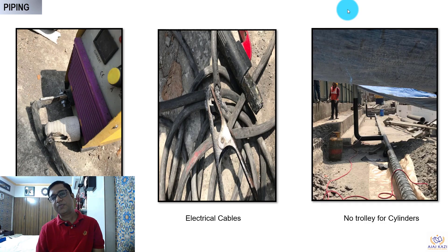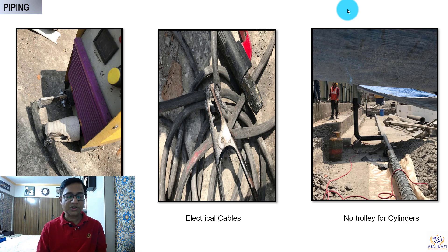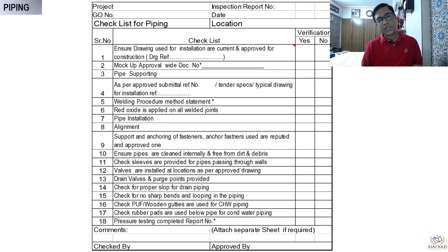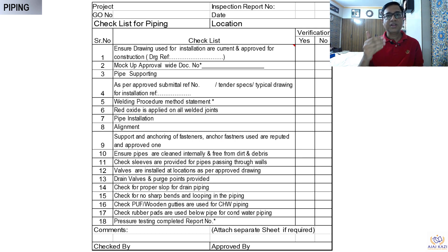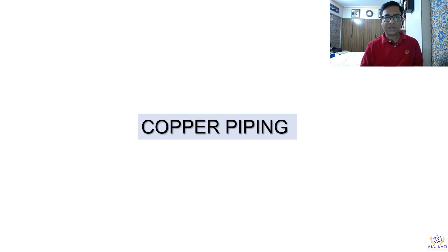We can see some common problems at site — the kind of welding machine, the cables, and the way oxygen cylinders and other cylinders are handled. A small checklist for piping covers most things: whether the drawing is available, whether the mock-up is approved, whether the specs are followed, and whether the best practices are followed. Everything is mentioned in this checklist, and it should be checked when piping work is done.